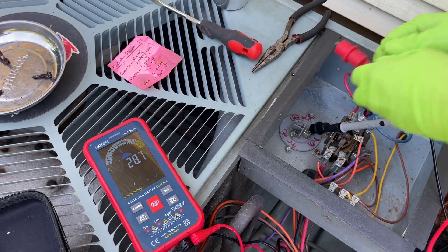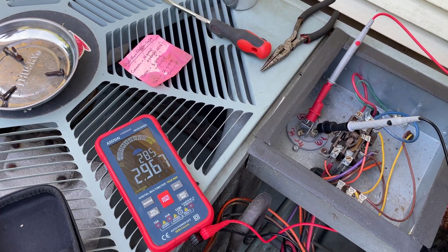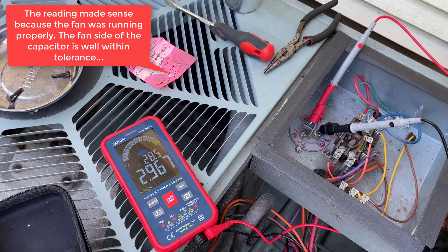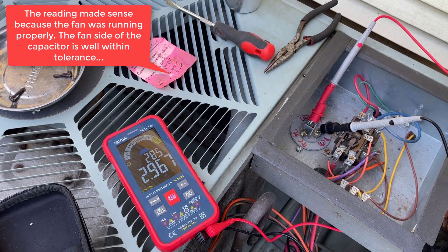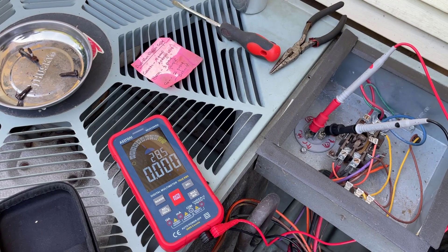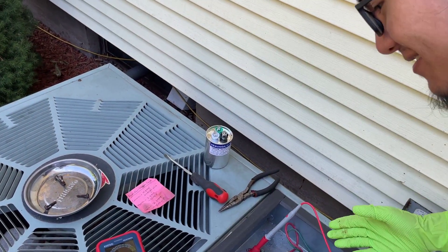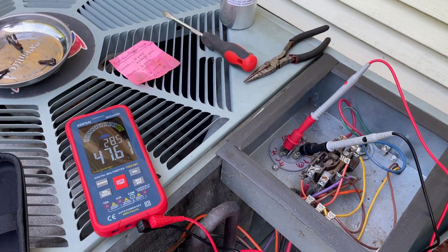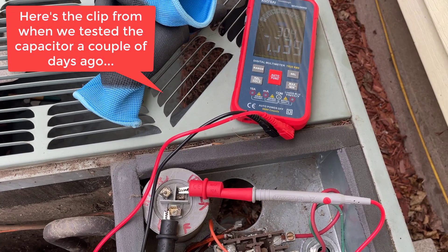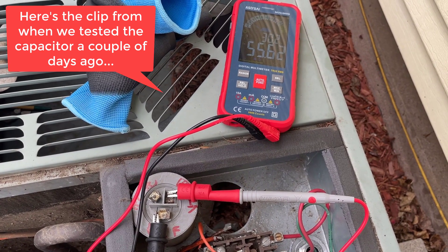Let's try the fan. It reads 29.6 microfarads, which is still within tolerance, but the compressor seems to be our issue. That's just almost out of tolerance, and that might be just enough that the capacitor is bad. We have tested this capacitor before, and every time we tested it, it gave us different readings — once it was out of tolerance, and one time it went from zero to infinity. We did test it with the wires disconnected.